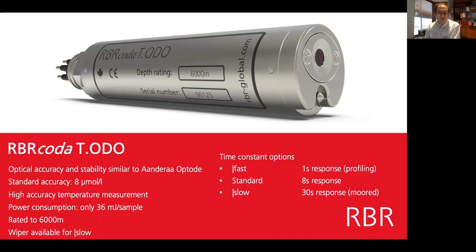We have 3 different flavors of this sensor, and each one has a different foil technology and therefore a different time constant. We make what we call the RBRcoda T.ODO Fast, which has a 1 second time constant, and that's typically used for vertical profiling. We make the standard, which is an 8-second response, and we have a slow one, which has a slower response, typically used for moored measurements, but there's a cover over the foil that protects the foil and allows it to be wiped. So you'll wipe biofouling off that, and we'll speak about that towards the end of the presentation.